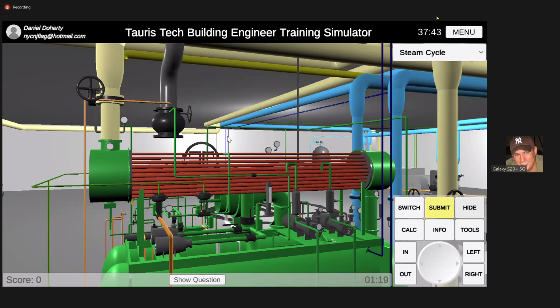So the steam's coming in through the exhaust, right? And then how is that steam condensing inside the surface condenser? What's causing it to condense? Vacuum? Kind of. But what's really causing it to condense? The condenser itself, the coils. That's it.